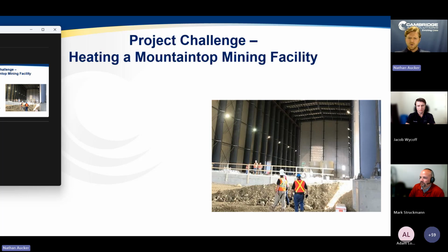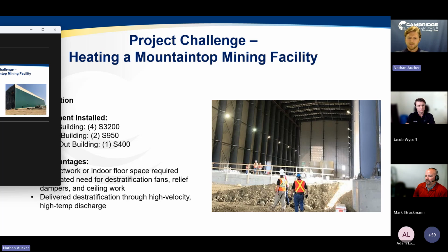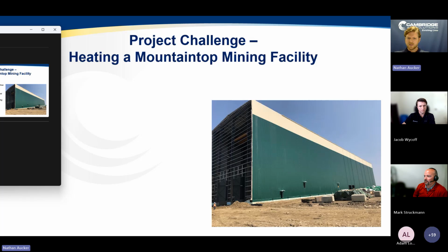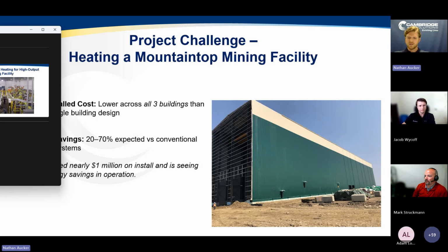And so when we were brought in to evaluate this opportunity, it really came down to, for one of the buildings, 4 units, and for another of the buildings, 2 units. And then for the last building, just a single unit, and really no ductwork or indoor space required, eliminating a lot of the extra needs, and really dramatic results with the high velocity, high temperature discharge at destratifying. And interestingly, the solution was actually a lower cost across all 3 buildings than the original single building design, which is just a fascinating example of the value that this can provide in these types of applications.